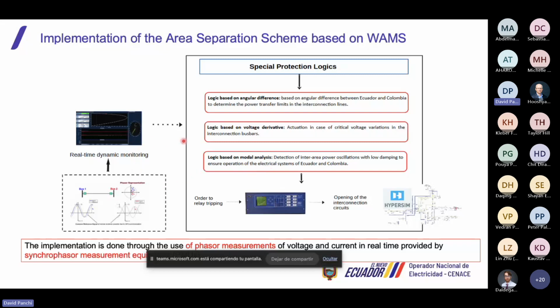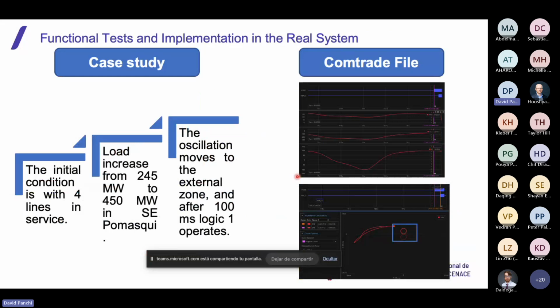So here we can see that if a logic sends a trip to the relay, the relay sends the trip to HYPERSIM, but the logics are implemented in the WAMS system. So the WAMS system controls the relay tripping, and this relay sends the trip to the simulator again. So it's a software-in-the-loop architecture, and we have hardware too.